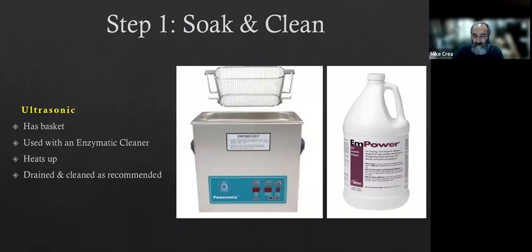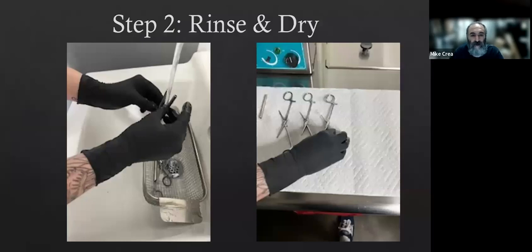And then when it comes out of the ultrasonic, we have to rinse them off and let them dry. So you can see here, we are rinsing the tools once they come out of the ultrasonic. Once they are rinsed off, because you have to rinse off all the enzymatic cleaner that's on there, you need to lay them out to dry. You never want to package up wet tools because the package can rip when you're packaging it up, or some of the water can splash and get into your eyes, or get into a cut, or get into your clothes. So we don't want any contaminated water getting all over us. So we always want to make sure we lay them out to dry first before we package them up.